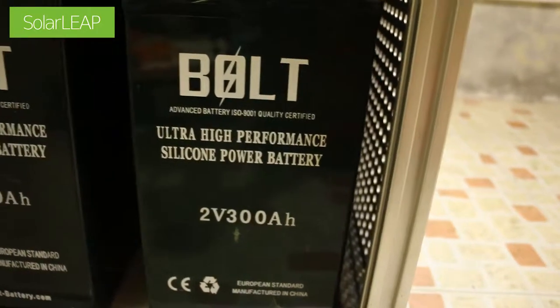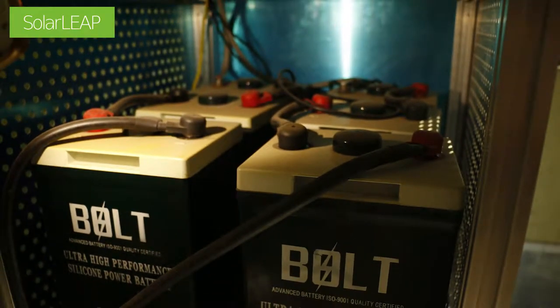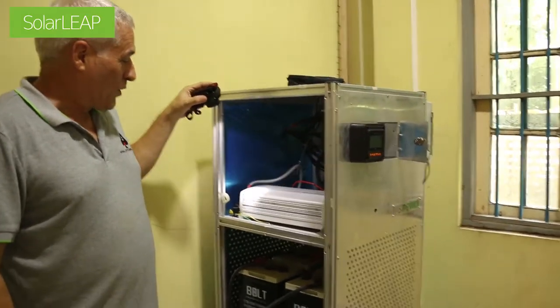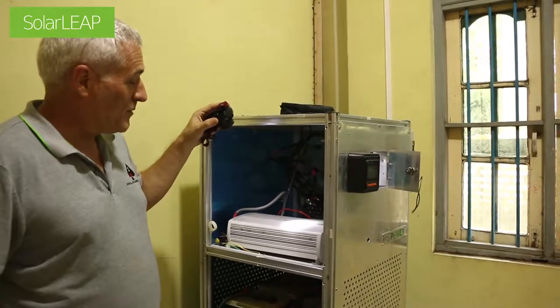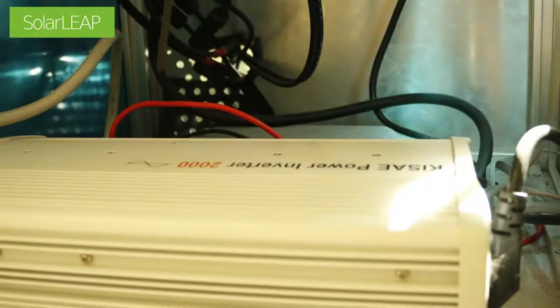These are 2 volt, 300 ampere hour each, so we end up with a 24 volt system. It basically consists of the battery pack, and then we have an inverter here which converts DC power into AC to run all the equipment and produce 2000 watts of power. We also have a solar charger inside here.